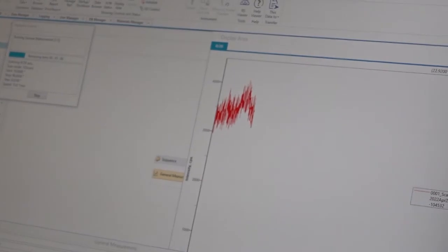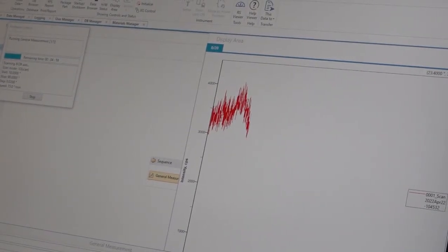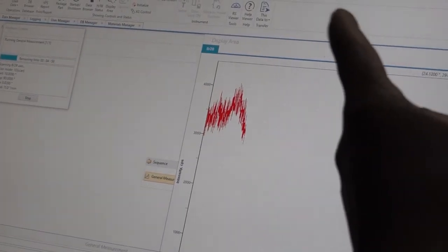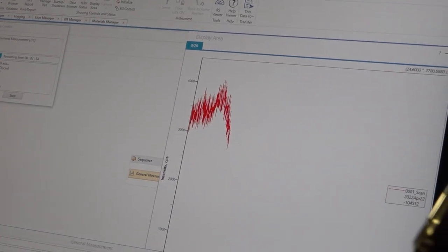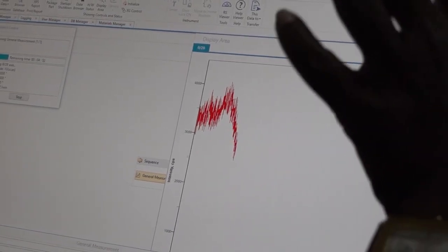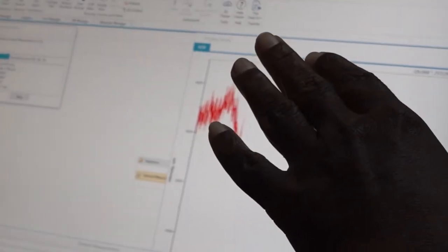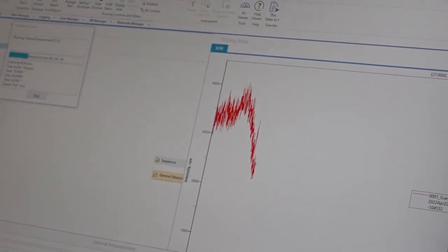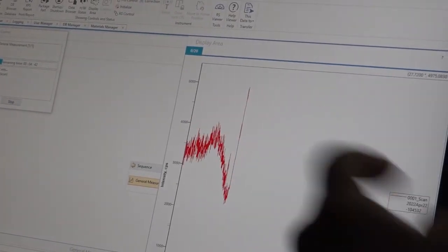You have to switch off here. Then one more switch is there at the back, the MCB. That you switch off. But when you switch off the X-ray now, the chiller will be on for up to 3 or 4 minutes. You have to wait till the chiller switches off. After that only you can switch off. But the computer you can shut down. After switching off the chiller only, you can switch off the main instrument.